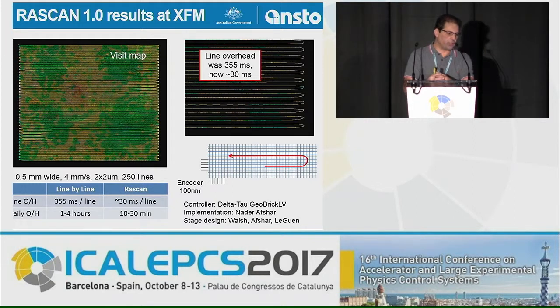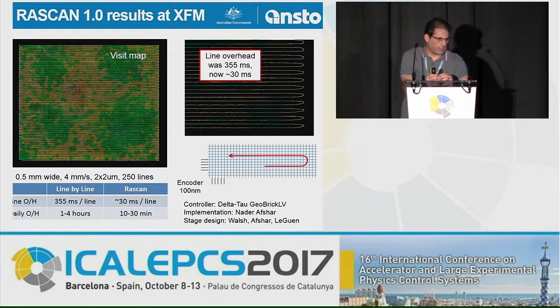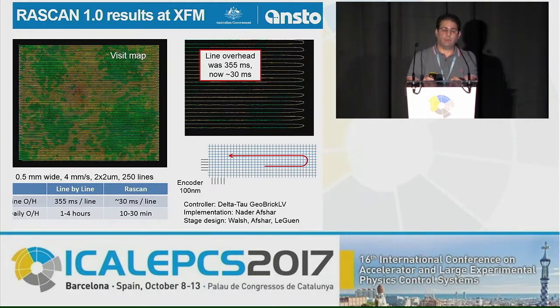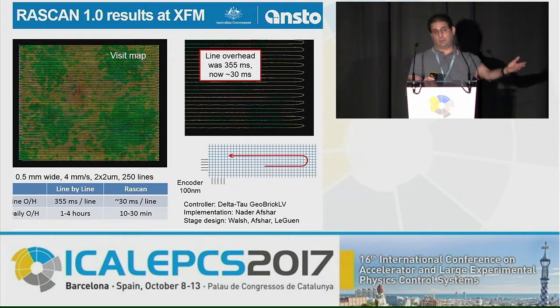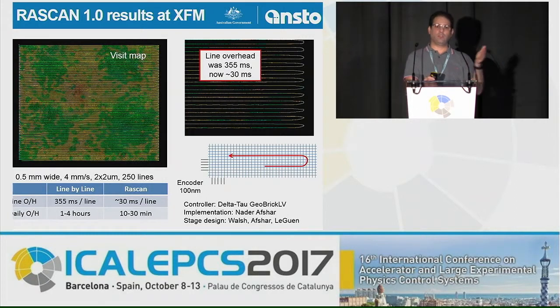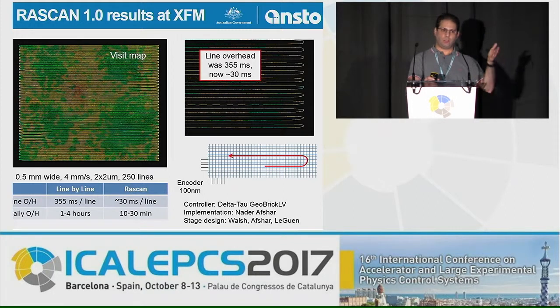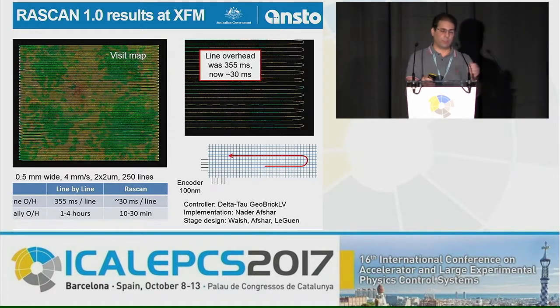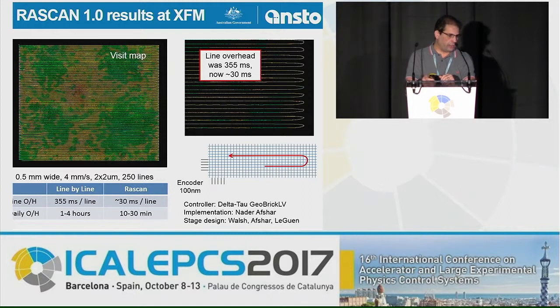First results: this is a visit map, where the detector listens to positions — capturing positions without the beam. On the right you can see the trajectory is precisely tracked by the stage. Part of this is because it's a very well-tuned stage, but also the trajectory is kinematically optimized, making it easy to track. The overhead times are now down to 30 milliseconds, which has been saving hours of beam time — approximately four hours per day in XFM. It is implemented on the Delta Tau Geobrick LV.